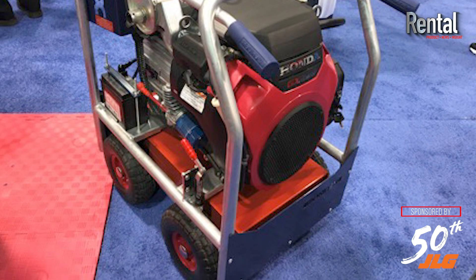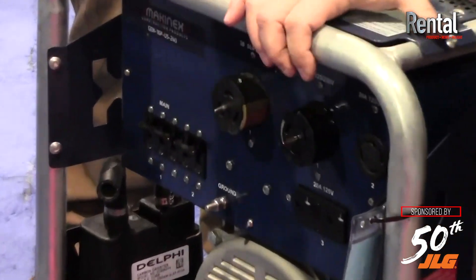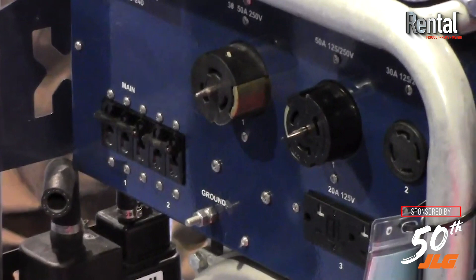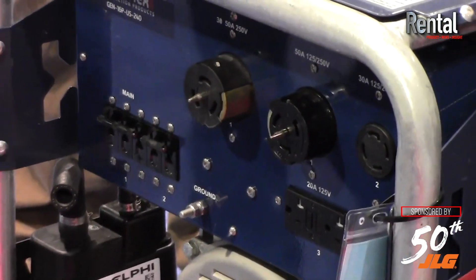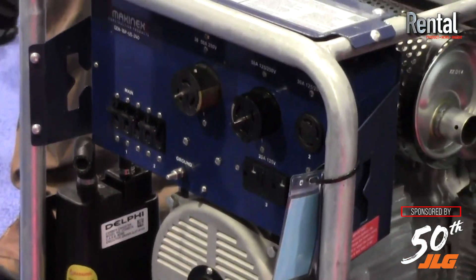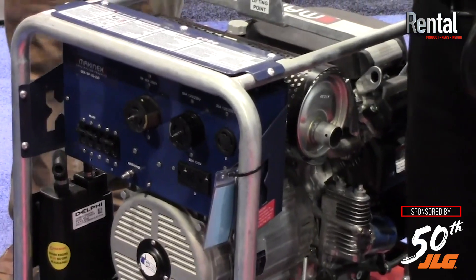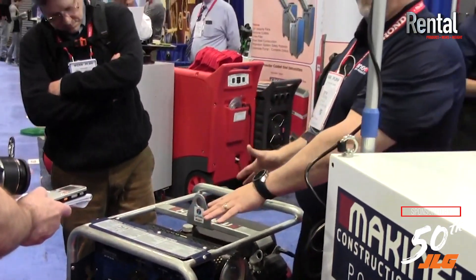It allows you to run both of them at the same time. We've got 50 amps on either leg and 20 amps of 120 power. It'll run for eight hours at 75% load on a single tank of fuel, and it takes portability to a new level where most people are normally used to bringing in tow-behind machines to power the equipment they need. We've put together a much smaller footprint, and the majority of that is due to the alternator that we use.